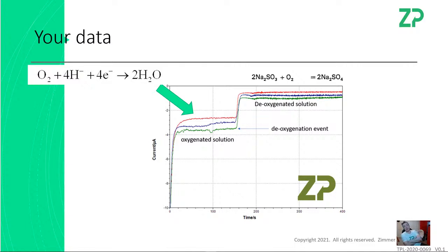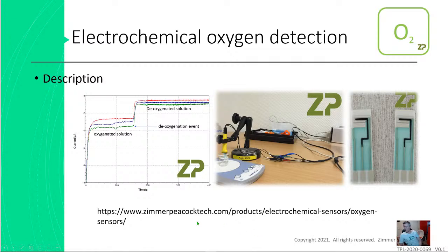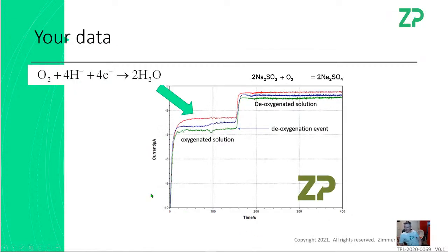But at ZP we don't often use a potentiometric mode for oxygen. We actually use the amperometric mode, which means a different board, and essentially not the platinum electrode, but actually an oxygen electrode that we also have on the website. It's not easy getting into biosensors. There's a lot of nuances, and that's why we do this webinar once a week, because we know it's not necessarily straightforward.